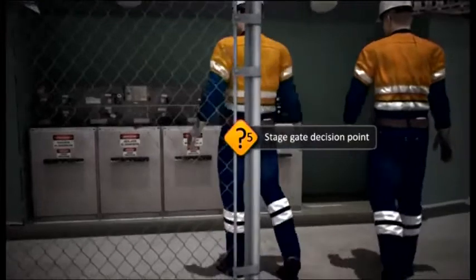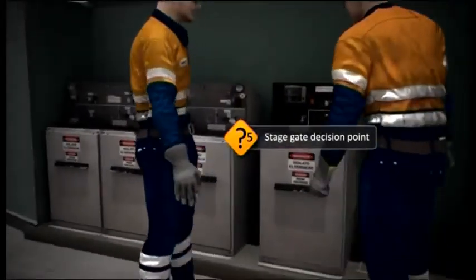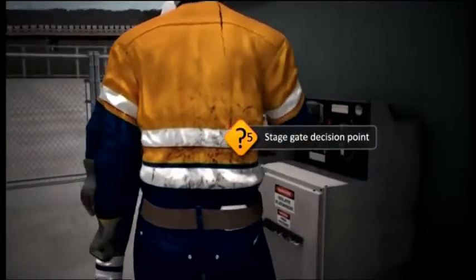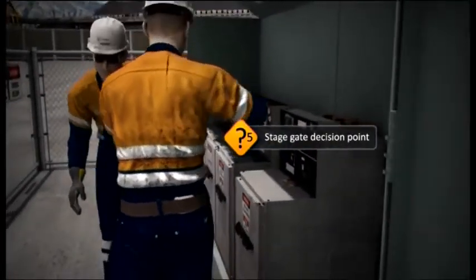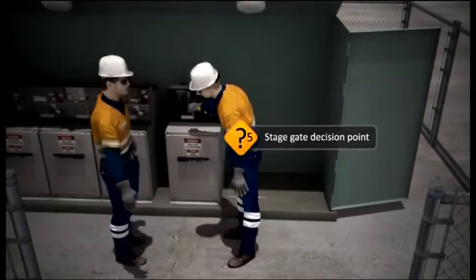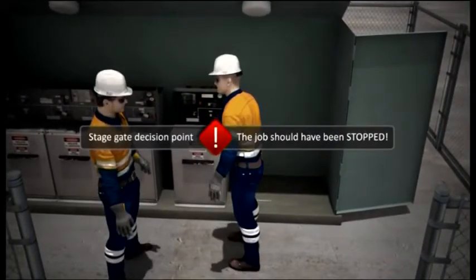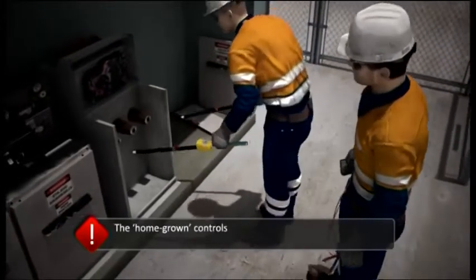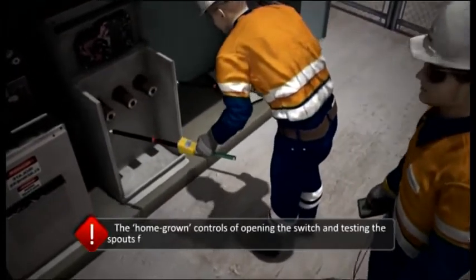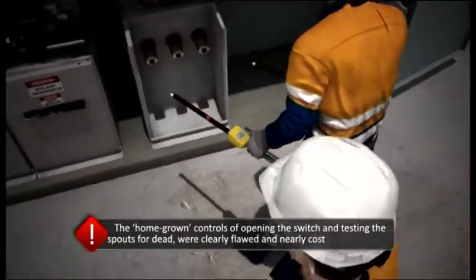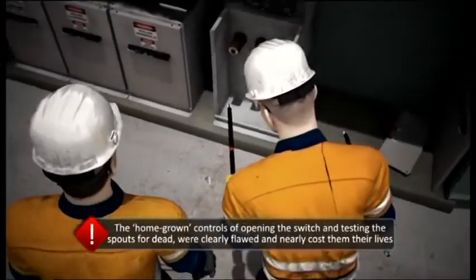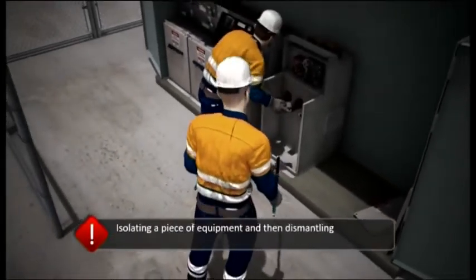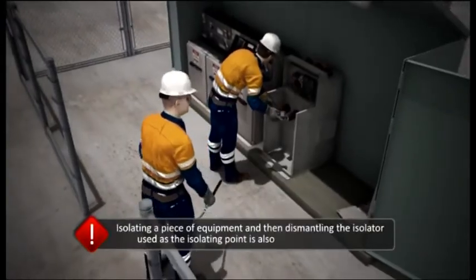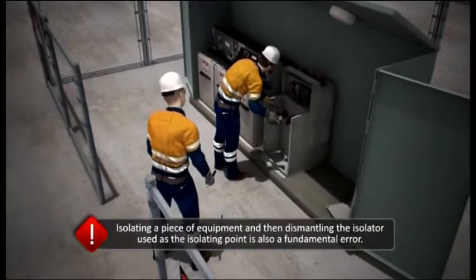Finally, the decision to open the high voltage cabinet without following the correct isolation procedures and obtaining the proper permits is a clear breach of practice and can never be tolerated. The job should have been stopped until the necessary authorizations were obtained. The homegrown controls of opening the switch and testing the spouts for dead was clearly flawed and very nearly cost them their lives. It should also be noted that isolating a piece of equipment and then dismantling the isolator used as the isolating point is also a fundamental error in isolation practices.